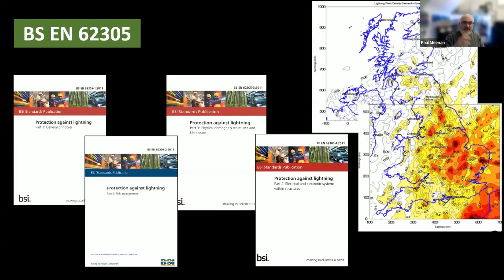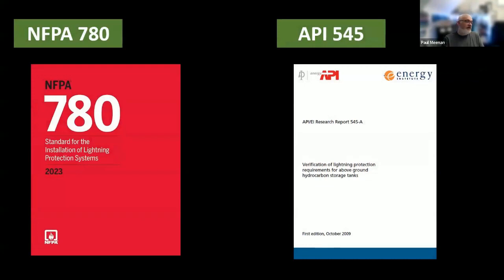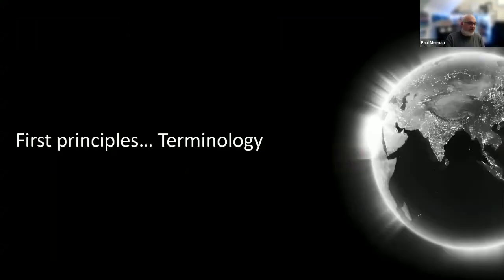If you don't have a risk assessment, then in England, you'll be told to go away and look at 62305. It does need an update, in my opinion, and it probably needs an additional one as well for testing. So there could be a part 5. Just again, my opinion, it would be great to see a standard on testing of lightning protection so that we can harmonize that a little bit better. Again, further afield, for lightning protection, NFPA published 780 again this year, the standard for installation of lightning protection. And there are also some secondary research documents, API 545 from the Energy Institute, on verification of lightning protection in specialist areas. So there are lots and lots of standards, and that was just a summary of some of them.